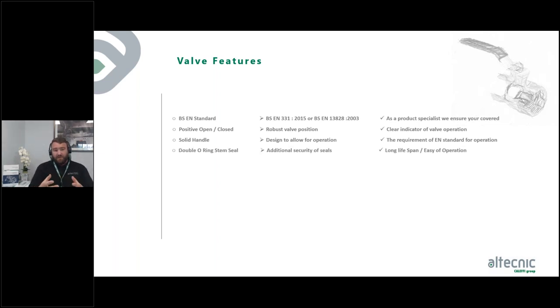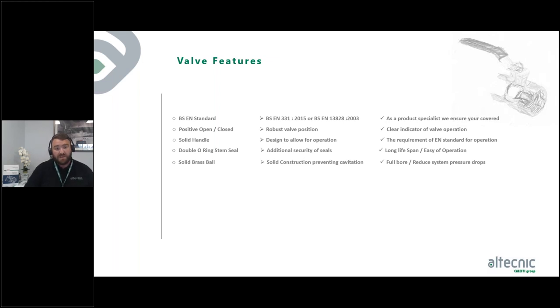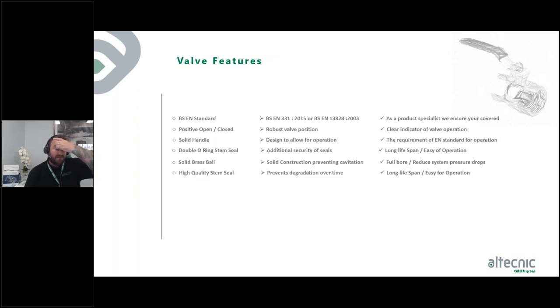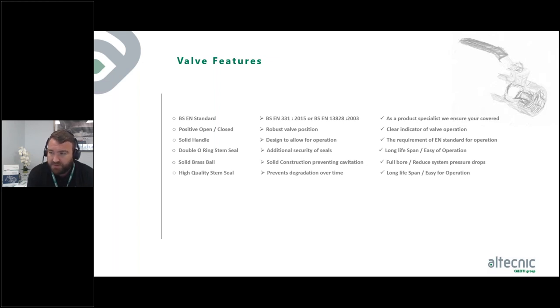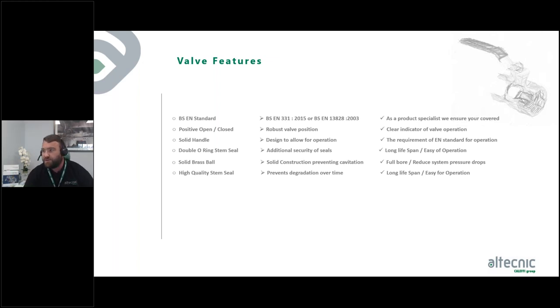The double O-ring on the stem provides additional security for the seal, a longer lifespan, and ease of operation. We also have a solid brass ball — solid construction prevents cavitation; some cheaper valves on the market are only coated rather than solid, and cavitation can cause corrosion over time. Our full bore system reduces system pressure losses. High-quality stem seals are also important: lower-quality materials can harden and become brittle over time, making the valve difficult to operate, so we use high-quality material to ensure the same smooth operation every time.